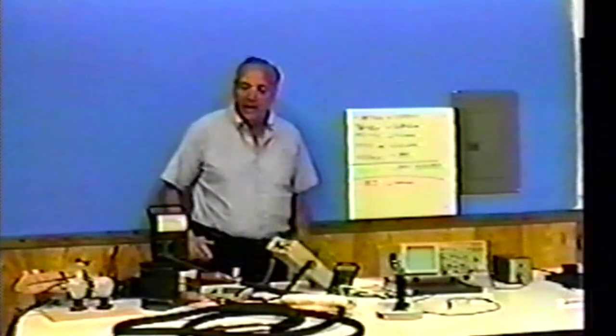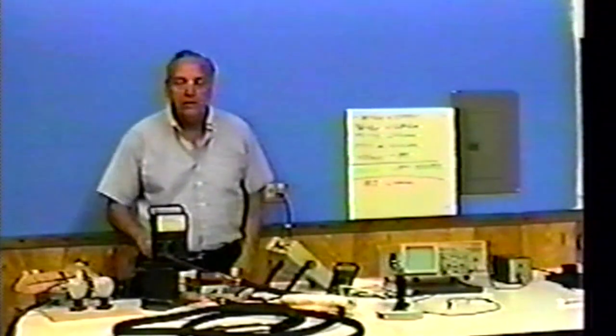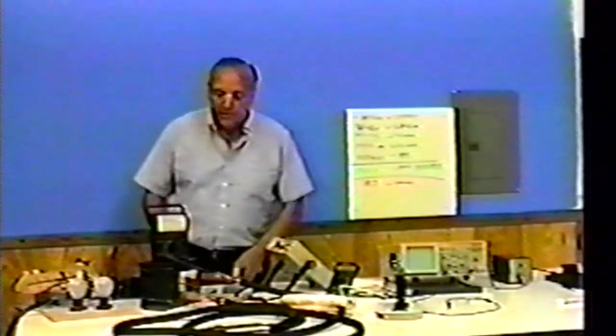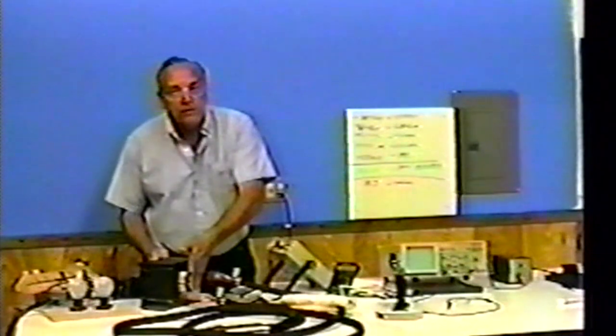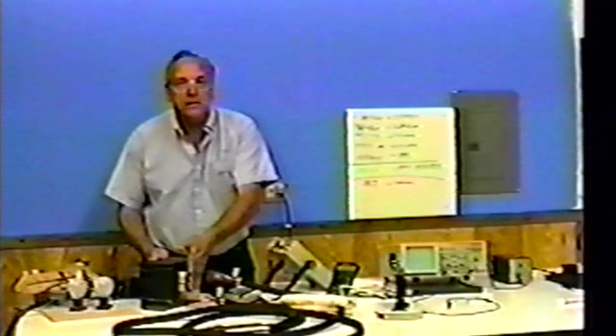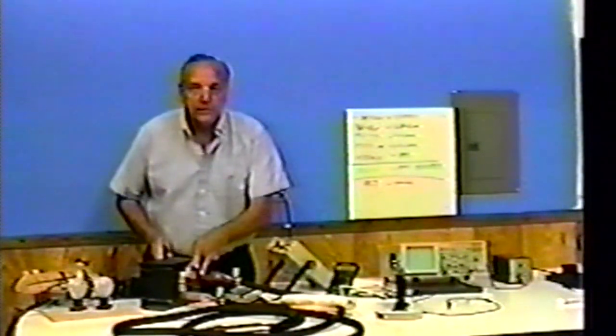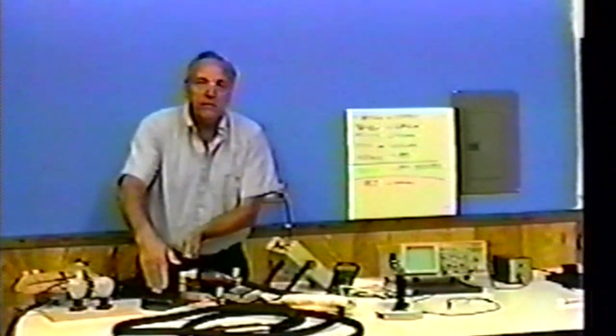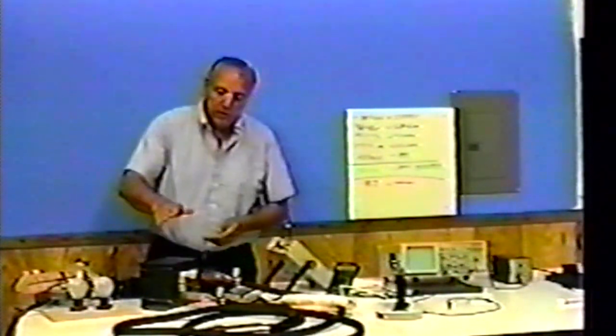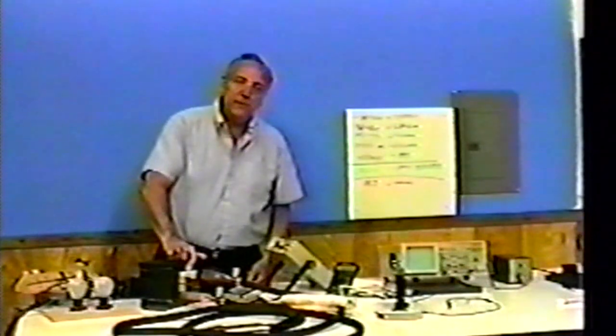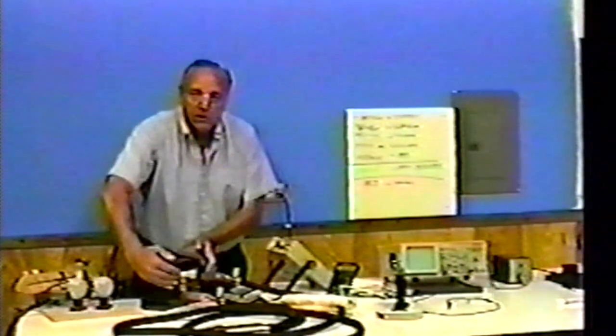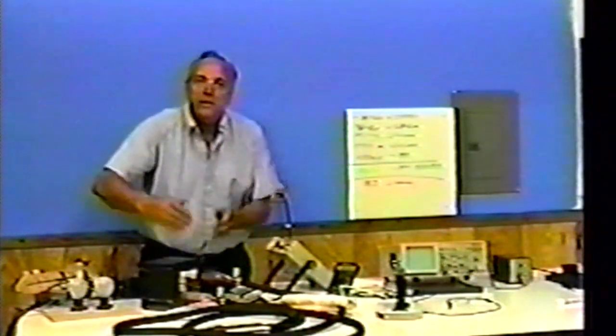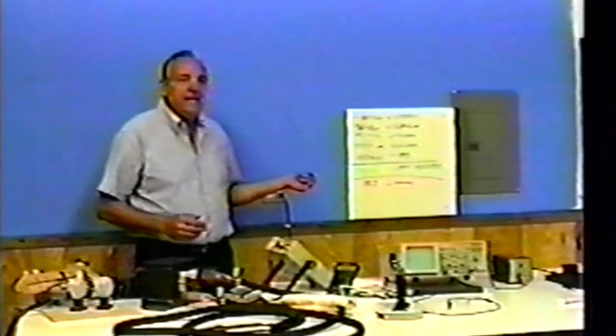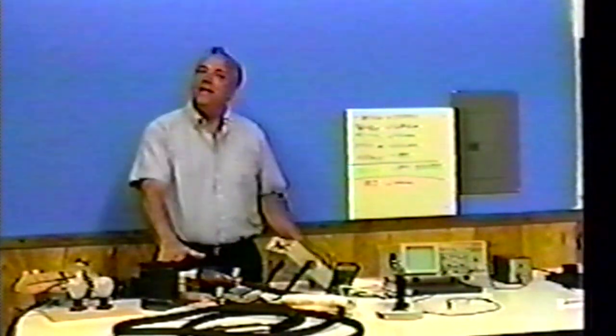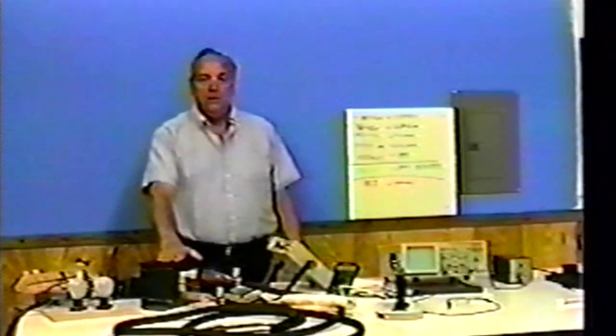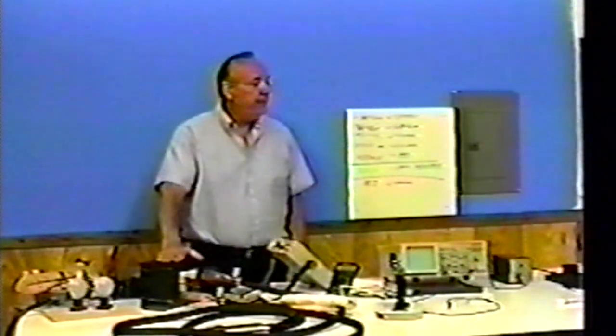In other words, 19% of the power we got going in is wasted inside the transformer. If you reach down here and feel, sure enough, that's starting to get warm. The iron gets warm. There's a loss in the iron, a loss in the primary, a loss in the secondary. It's all within the boundaries of the transformer, and you've got a 19% loss. A 19% loss on a transformer this size is a real good transformer. Most transformers won't perform that well.